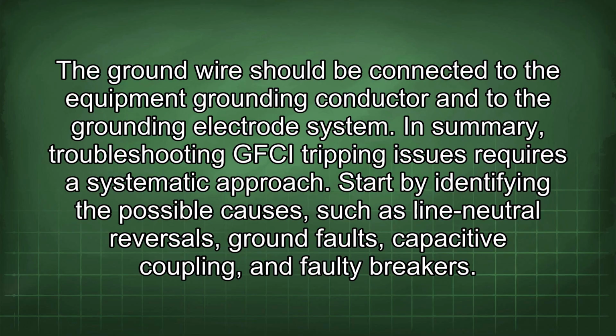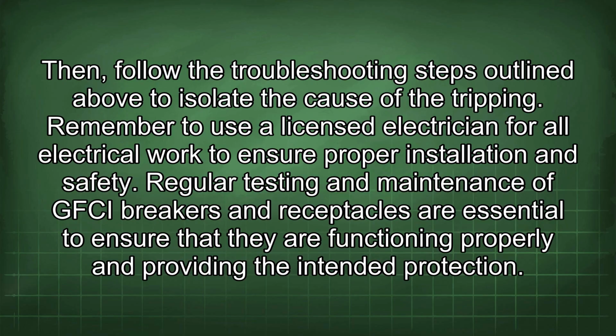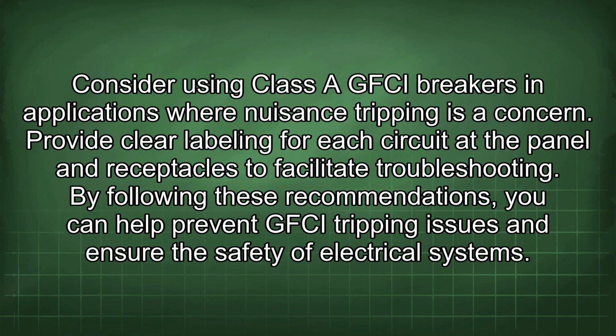In summary, troubleshooting GFCI tripping issues requires a systematic approach. Start by identifying the possible causes, such as line neutral reversals, ground faults, capacitive coupling, and faulty breakers. Then, follow the troubleshooting steps outlined above to isolate the cause of the tripping. Remember to use a licensed electrician for all electrical work to ensure proper installation and safety. Regular testing and maintenance of GFCI breakers and receptacles are essential to ensure that they are functioning properly and providing the intended protection. Consider using Class A GFCI breakers in applications where nuisance tripping is a concern. Provide clear labeling for each circuit at the panel and receptacles to facilitate troubleshooting. By following these recommendations, you can help prevent GFCI tripping issues and ensure the safety of electrical systems.